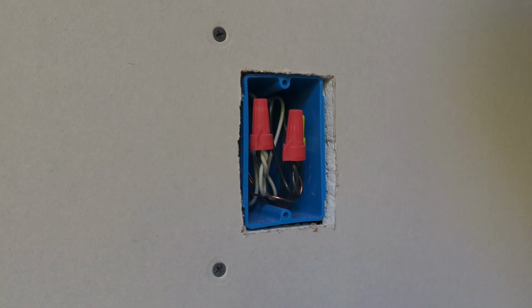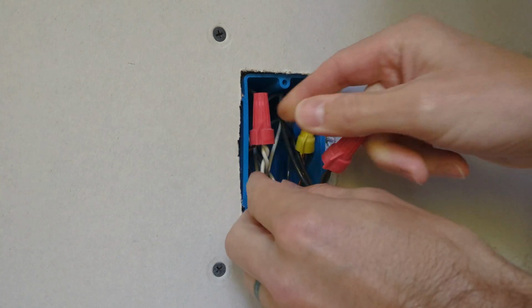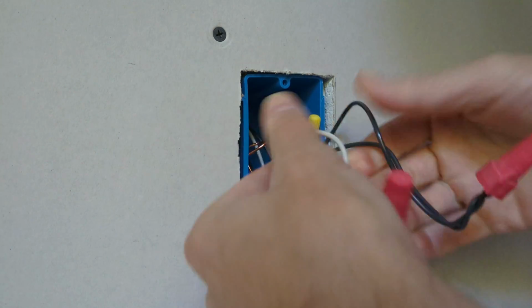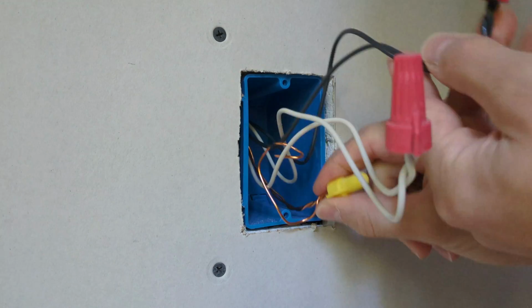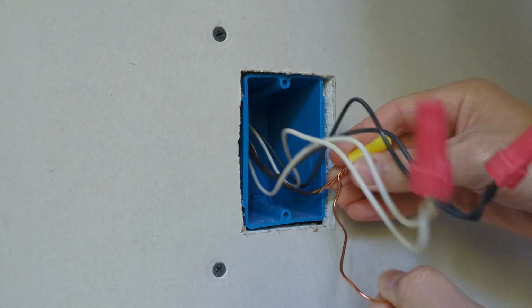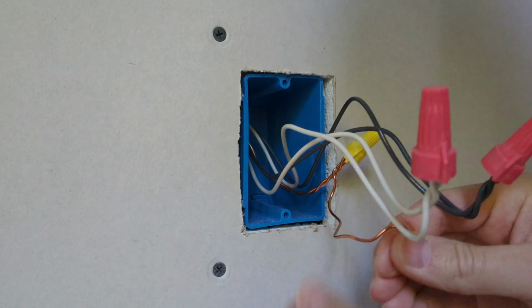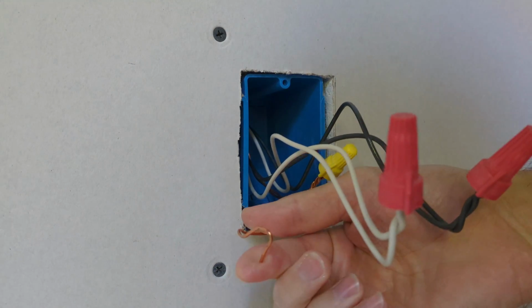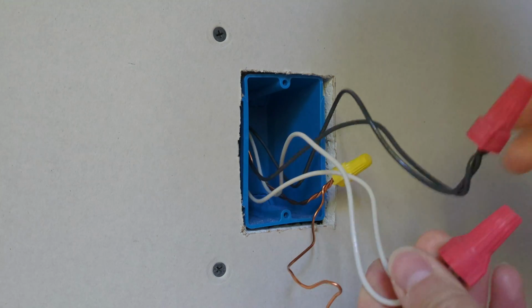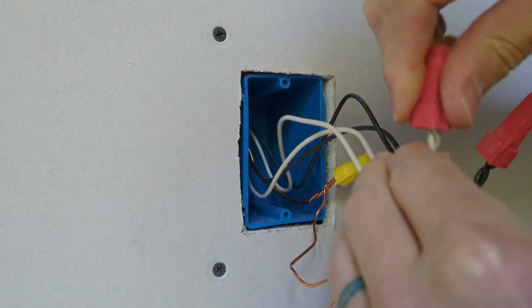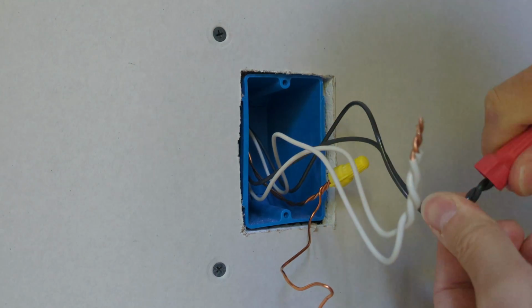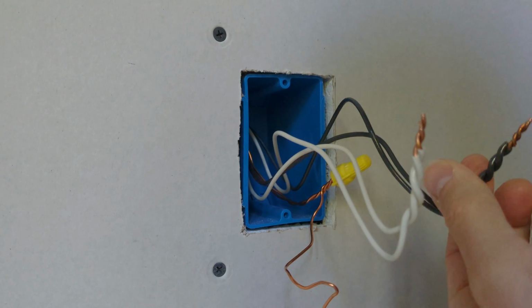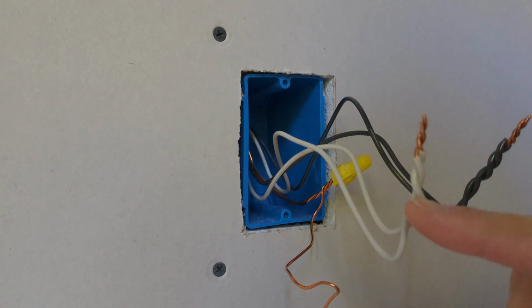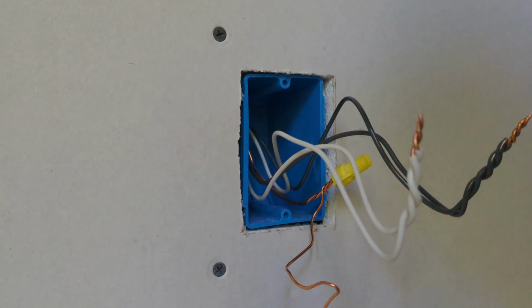First thing to do is shut off power. I already confirmed power shut off at the breaker. And we've got plenty of extra wire here to work with. See, we've already got the pigtail for the ground. I'll need additional pigtails for the neutral and the hot wire. This is 14 gauge wiring for a 15 amp circuit and 15 amp outlets.